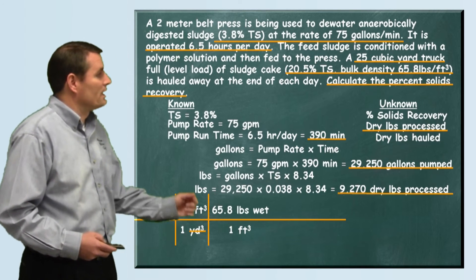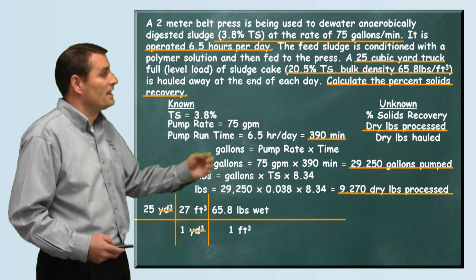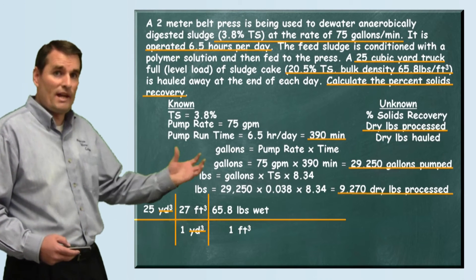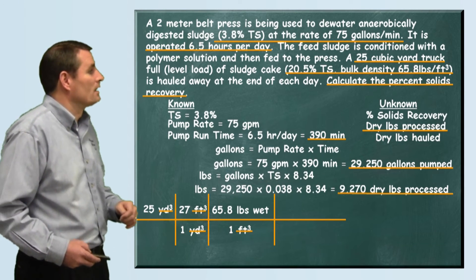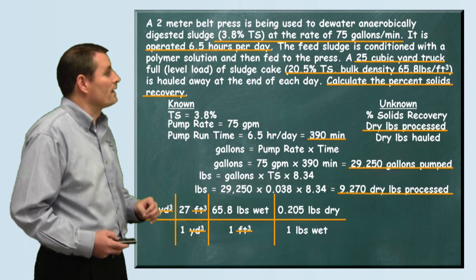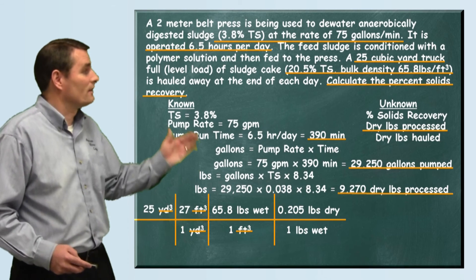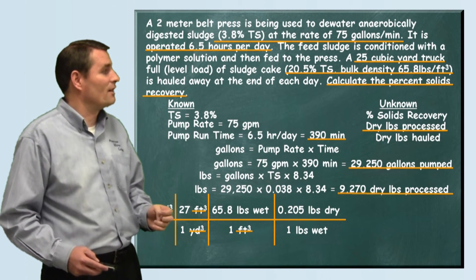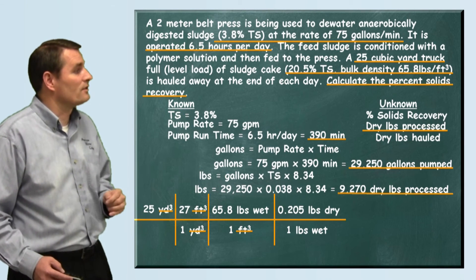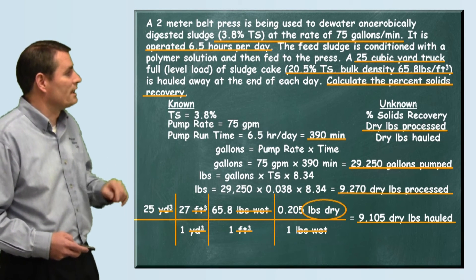Now we can use our unit conversion that they gave us. For every cubic foot of sludge it's 65.8 pounds wet. That's the weight of the wet sludge in the truck. They also told us that our sludge was 20.5 percent total solids, so we enter that in decimal form as 0.205 pounds dry. For every wet pound, since it's 20.5 percent total solids, there's 0.205 pounds dry.